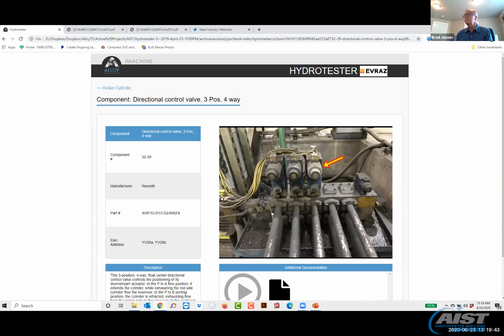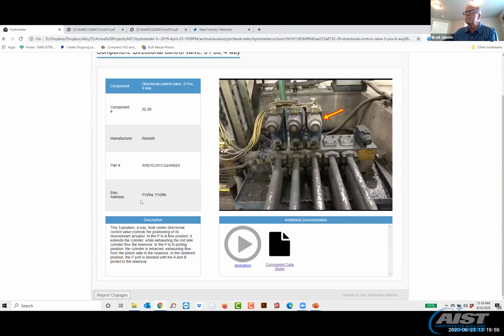So in addition to identifying where it's at and what it is, you have the manufacturer, you have the part number, and we'll get to this in a bit, but you have the electrical address, the controls, what's firing it. And then down here, you have a description of what that device is doing in that particular circuit. In other words, if you look at pressure valves, we basically have 5 different types of pressure valves. But within those 5 designated types of pressure valves, you can have various applications within each valve.